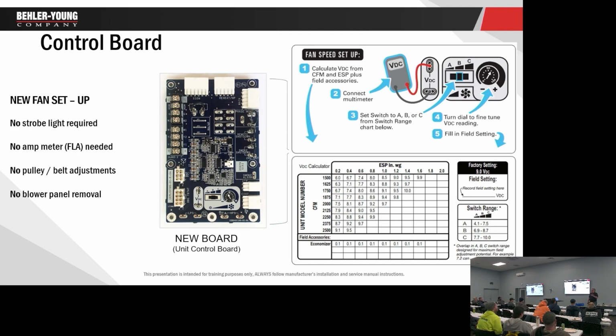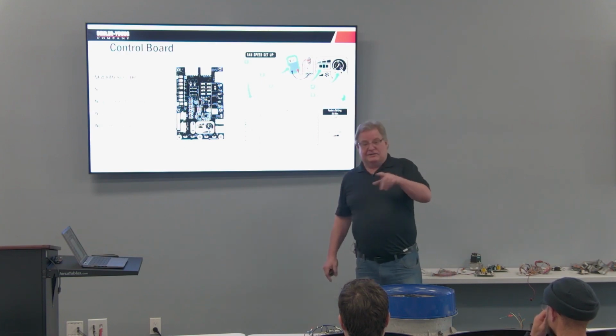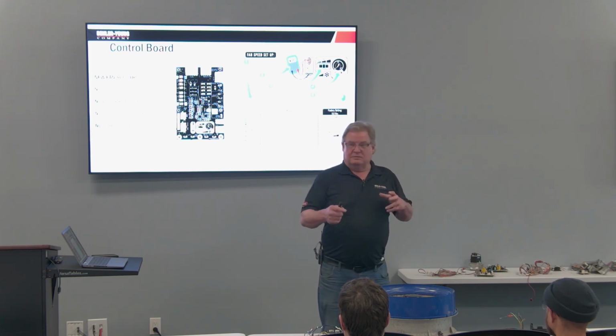So the first mistake you make, and how do I know this? Like most everything we learn, it's in the field. We learn by on-the-job experience, meaning we got paid to screw somebody else's stuff up. That's pretty much what it is. I admit, I learned this way myself. Out on the job, the motor's bad, we change it out. The new motor was the wrong voltage. It was a 3-phase, we had a single phase. So we put the old motor back in, and just for the heck of it, we turned it on and it ran. Well, wait a minute, it wasn't running before. Because what I didn't know was it had been shut off on its safety circuit.